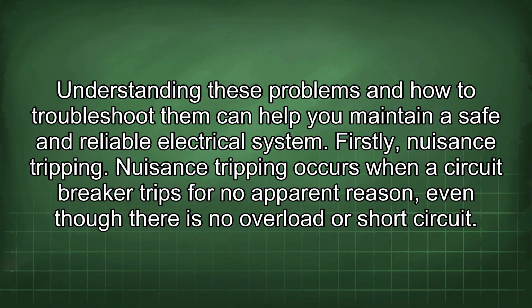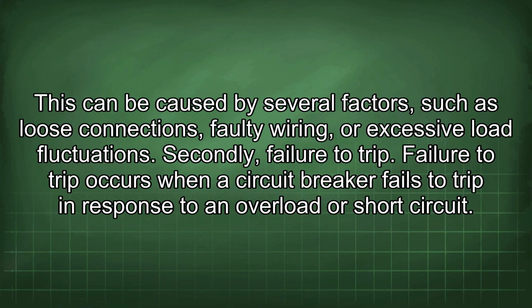Firstly, nuisance tripping. Nuisance tripping occurs when a circuit breaker trips for no apparent reason, even though there is no overload or short circuit. This can be caused by several factors, such as loose connections, faulty wiring, or excessive load fluctuations.